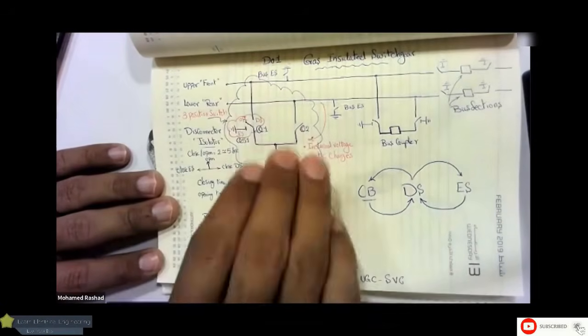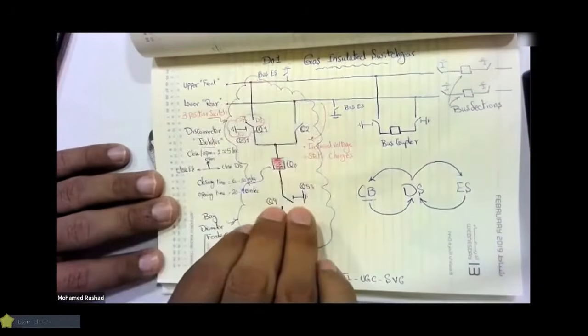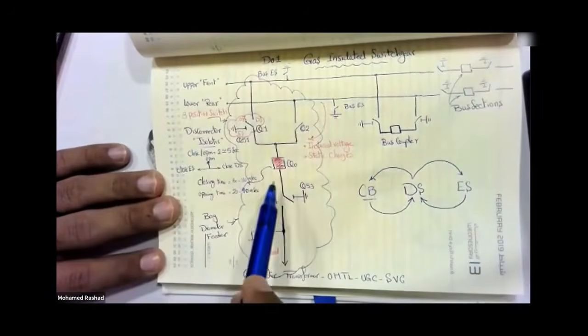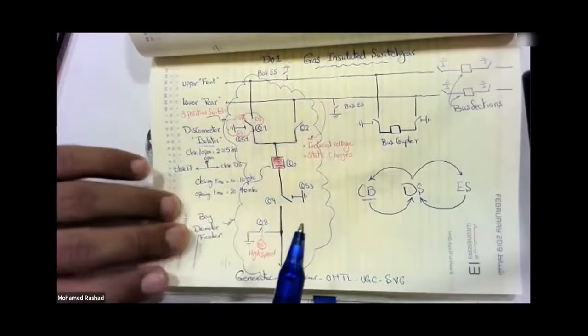All right, now to close the breaker. Now, to the right of this breaker, there is voltage, and to the left, what is there? To the left, there is voltage, right? So it could be live here and dead here, or it could be live here and dead here, or both could be what? Both could be live. That's why when we come to the breaker, we must have something called synchronization.